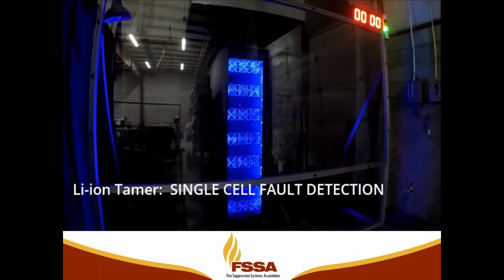This is the last video. This video is available online. You can go online and see many different types of off-gas monitoring systems and thermal runaway events that are available. But I wanted to play this video because it has a good timer up here that shows that critical time, that golden time that we talked about, of when off-gas is first detected and the difference between the off-gas event being detected and thermal runaway being achieved. So we'll want to pay attention to the bottom of this rack here, and when the clock starts is when off-gas is first detected.